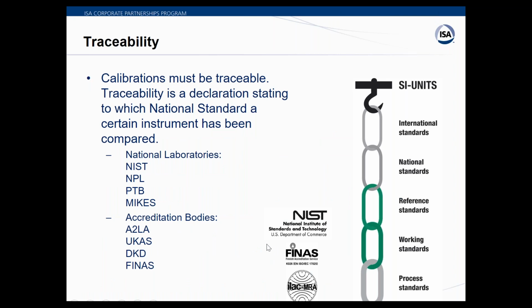The next thing when you talk about making quality measurements is you want to demonstrate traceability. So we have a chain or a pedigree. How do you get from your process all the way back to internationally recognized standards? And when you're doing calibration, traceability is one of the base requirements, and you need to have documentation that says what standard your equipment is traceable to. So in the United States, our national laboratory is NIST.